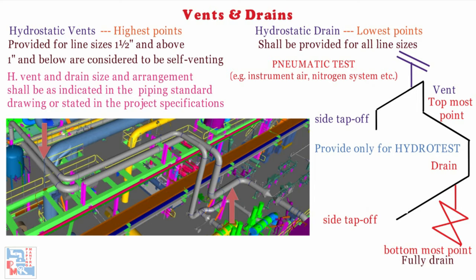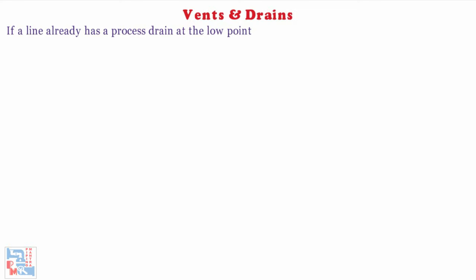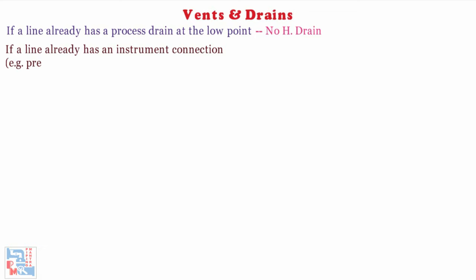Hydrotest drains shall not be provided if a line already has a process drain at the lowest point of the piping system — the process drain itself acts as the hydrotest drain in such cases. Hydrotest vents shall not be provided if a line already has an instrument connection, for example a pressure or temperature instrument, at high points of the piping system. This connection itself shall act as the hydrotest vent.